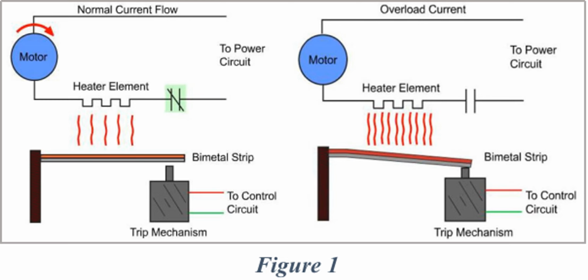Compositions. The composition of a thermal overload relay includes a heating component or element, a bimetallic strip, and an arrangement of transmission and adjustment systems. The bimetallic strip is the most crucial part of this relay. It is manufactured through the mechanical rolling of two metal strips of different linear expansion coefficients. The heating element is in the shape of a filament. It is composed of nickel-chromium alloy, copper-nickel alloy, or chromium-aluminium alloy. Due to its simple design, compact size, and low cost, a thermal relay has vast utilization in the production fields. Nurwati, Argianzia, Dofir, Hasana, Mayani, and Markovich, 2020, September.